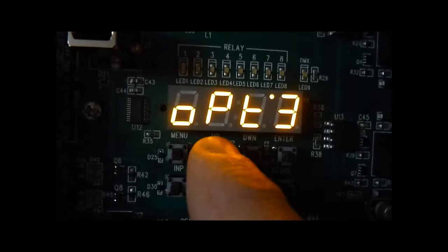Option 3 is maintain on closure, turn on assigned zones to a preset. On open, go to off. Option 4, default setting, maintain closure turns on assigned zones to a panic preset, and on open returns to normal control. Finally, option 5 is the demand response feature setting. It's maintained on closure, turns on demand response and load shedding. On open, returns to normal operation.